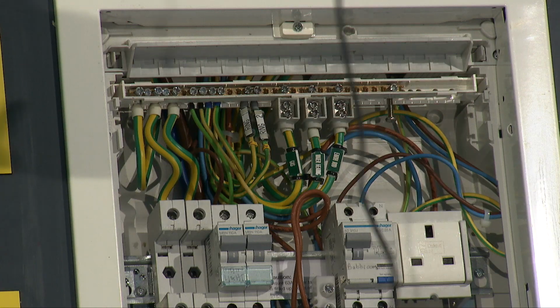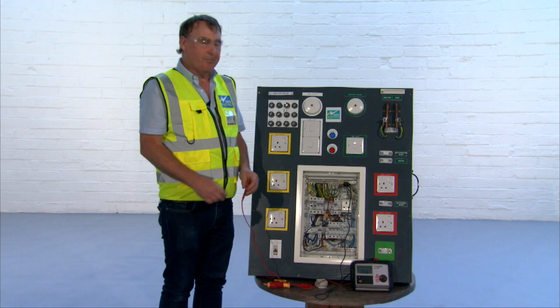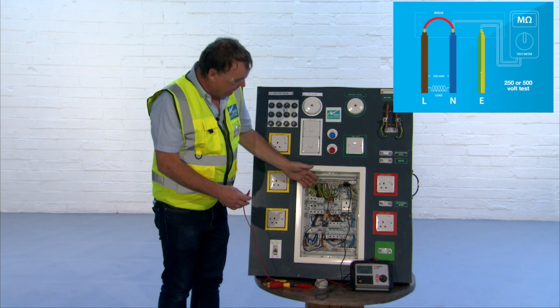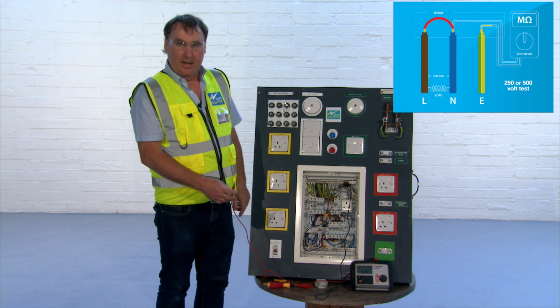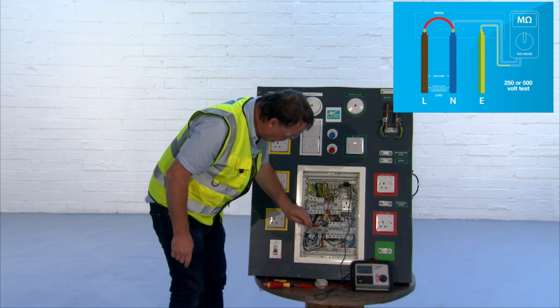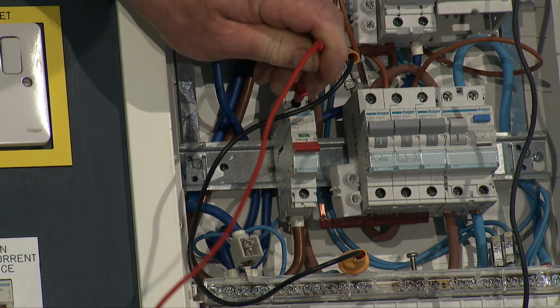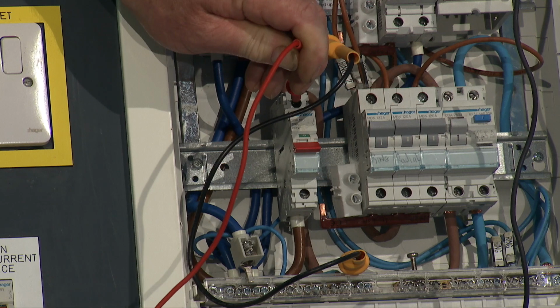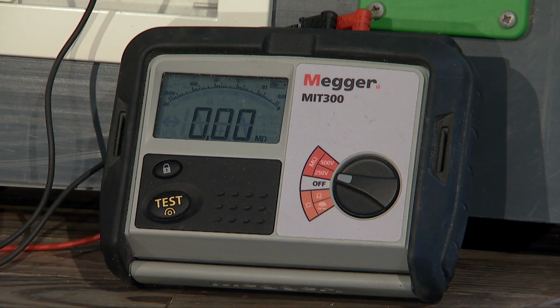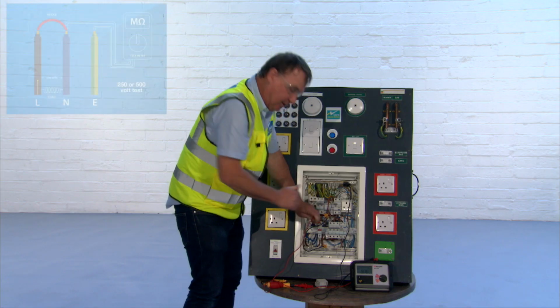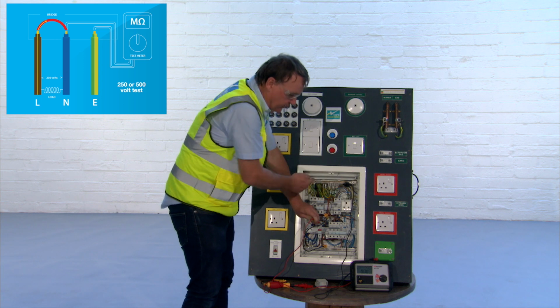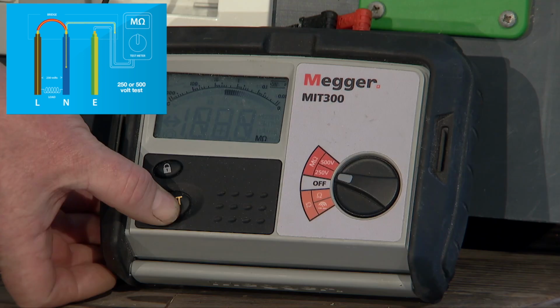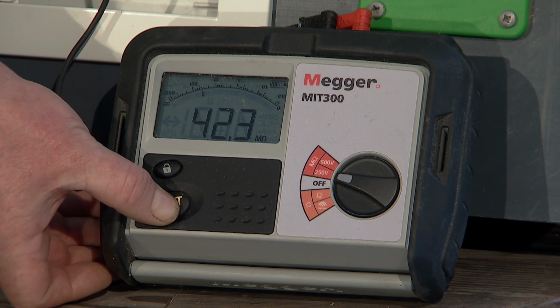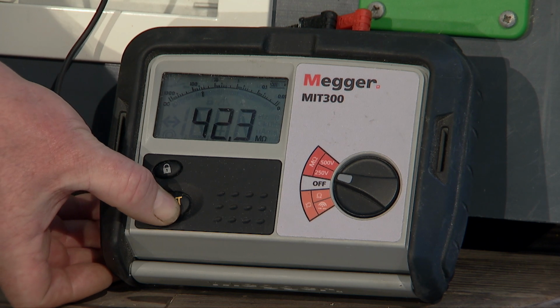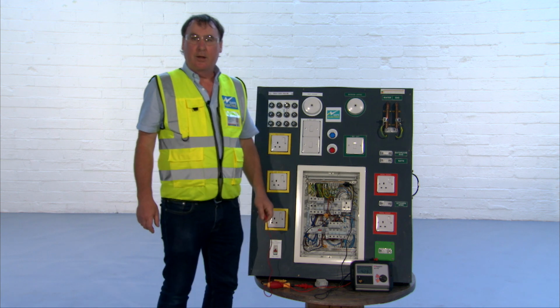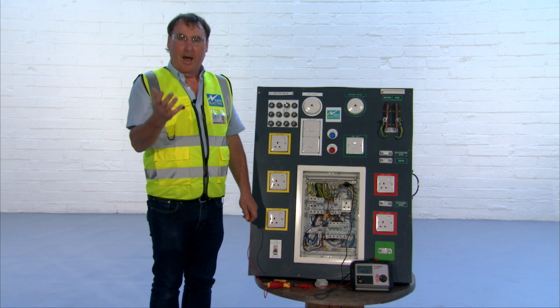We now clip one probe onto the main earthing terminal. This probe of our meter is now connected to every single earth or protective conductor in the installation. And we connect the second probe basically to the link. So we'll connect it here to the main live, which is now connected to the main neutral. So in this installation at the moment, all the lives and neutrals are connected together and connected to this probe. All the earths are connected to this probe. So we're going to press the button and we get our insulation resistance between all the live conductors and the protective conductors. And that insulation resistance is 42.3 mega ohms, which is a perfectly normal and acceptable reading.